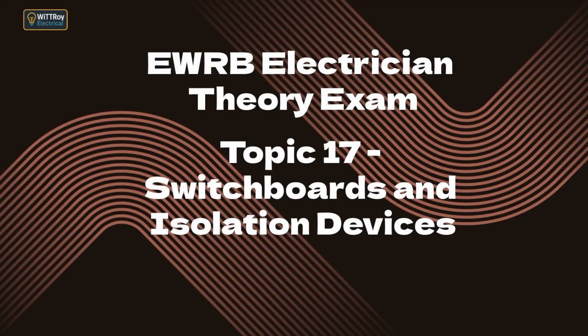A MEN switchboard has extra responsibilities because it includes the main earthing connection and the main earth neutral link. This means the neutral bar, earth bar, bonding connections, and MEN link must all be installed exactly as required by the standard. The physical connection must be secure, identifiable, and accessible for inspection. Because the MEN link plays a key role in the protection system, the switchboard must maintain low earth fault loop impedance and provide reliable bonding to all required parts.